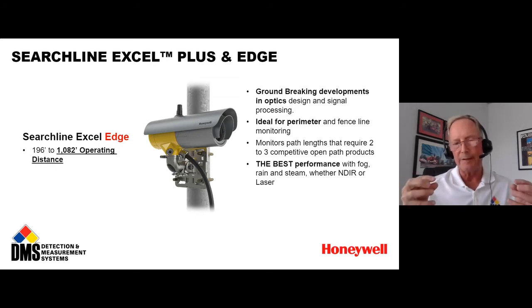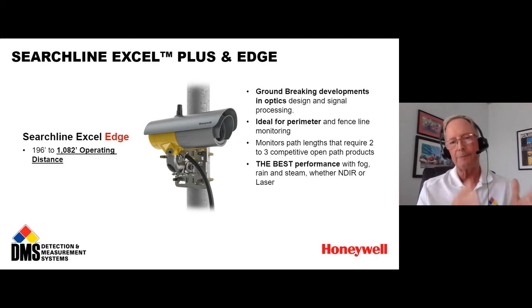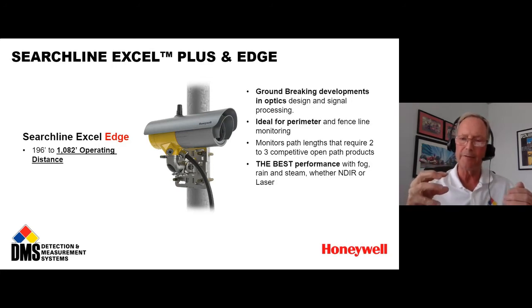When you've developed an optical bench or an optical system for an open path detector that has essentially doubled the operating distance of all of the competitive products on the market, that's great if you want to shoot it that far and cover that long of a distance. Which, by the way, that's a conservative distance. The product's performance is not being stretched at that 1,082-foot distance. But in other applications where you're shooting at 300 feet or 400 feet or 500 feet, you still have that very, very intense IR beam. Because it's so intense and because of the design of the optics that makes the most of it, this detector dramatically outperforms every other product on the market in cutting through fog, steam, and rain.